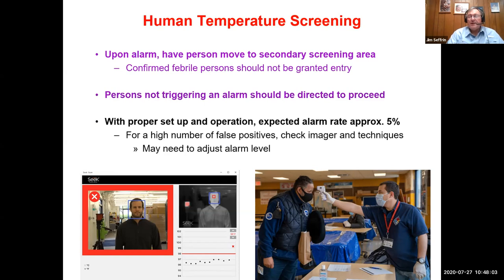With proper setup and operation, this is a question I get a lot. What's your expected alarm rate? Your expected alarm rate should be about 5% or less. If you're going above 5%, you either have a very high population of people indicating febrile. Now, I'm not saying it can't happen. There are places where COVID-19 is running rampant. So you could have a higher rate, but the expected alarm rate would be around 5%. Should you have a high number of false positives, check your imager and your inspection techniques, and you may find that you need to adjust your alarm level.